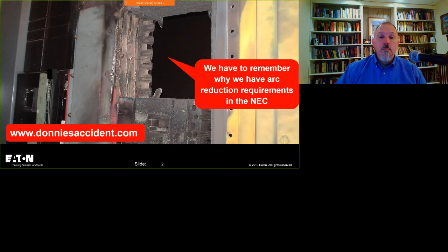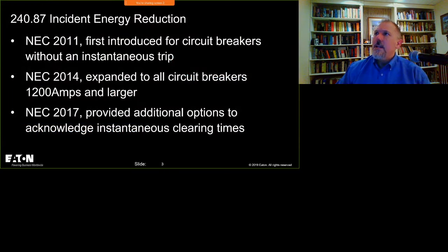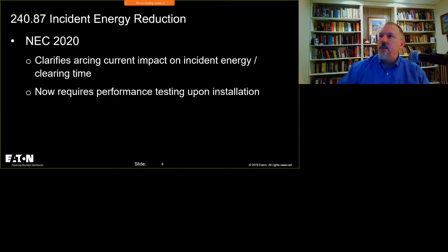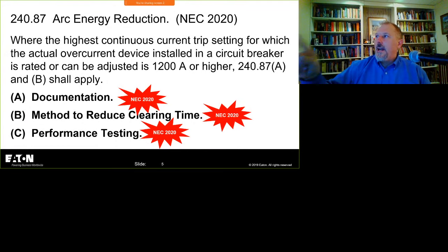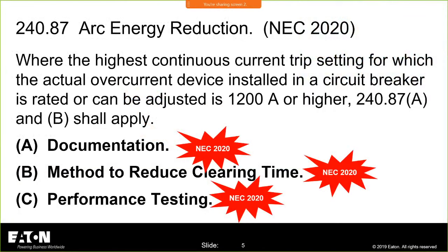All right. We're going to move this train forward. NEC 2011. We already talked about this. I'm not going to dwell on it. It entered in the 2011 code. It's been continuously changed. And the big thing in the 2020 cycle is they clarified the arcing current and the clearing times. Again, where the highest continuous current, just to give you that, where the highest continuous current is set trip setting. So what they're telling you, they took this language from 230.95 and other areas in the NEC where we talk about 1,000 amp devices in GFPE. So it's similar language that you've seen there.